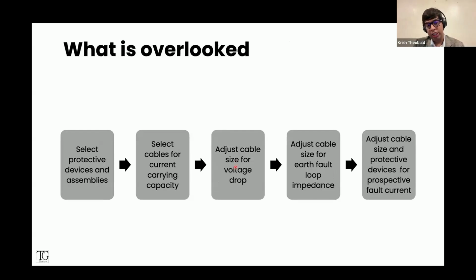So this is the whole process, but what we often overlook in India, unfortunately, is that we don't really select protective devices and assemblies. We just tend to use what is available. Sometimes when we do, it's more of a thumb rule rather than an actual calculated approach. We've also got cable selection for current carrying capacity. We often select cables for load. We don't actually follow the correct process, and I'll show you what that means.